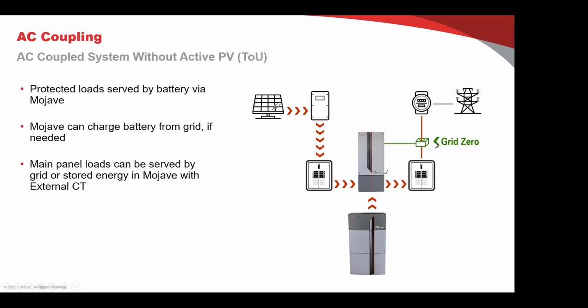And here is what we call a grid zero point. So we're not exporting to the grid, and we're not importing from the grid. We send just enough energy to power these main panel loads, and we zero the grid at this point. So if we see energy starting to be exported, then we reduce the power going to the main panel. If we see that we're starting to import, then we increase power going to the panel. So we use this external CT to maintain that zero point.